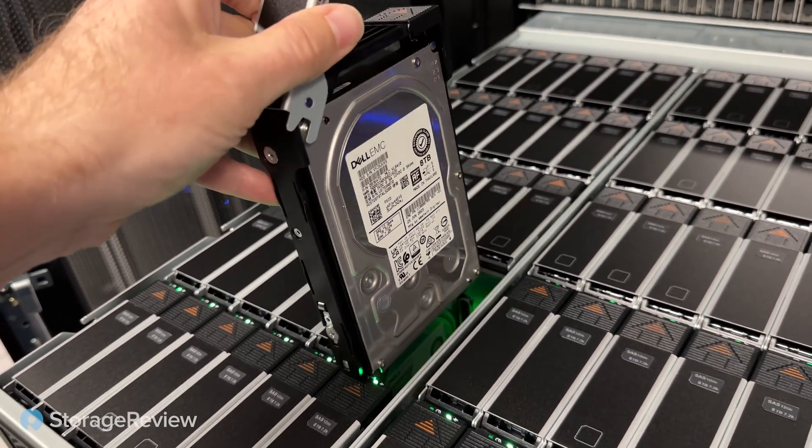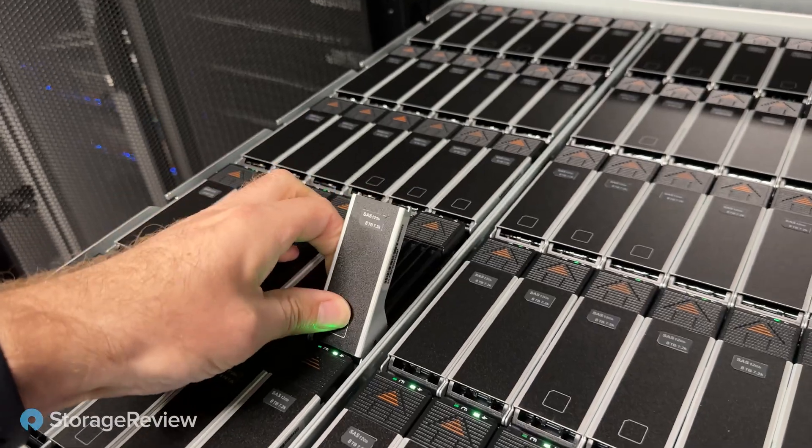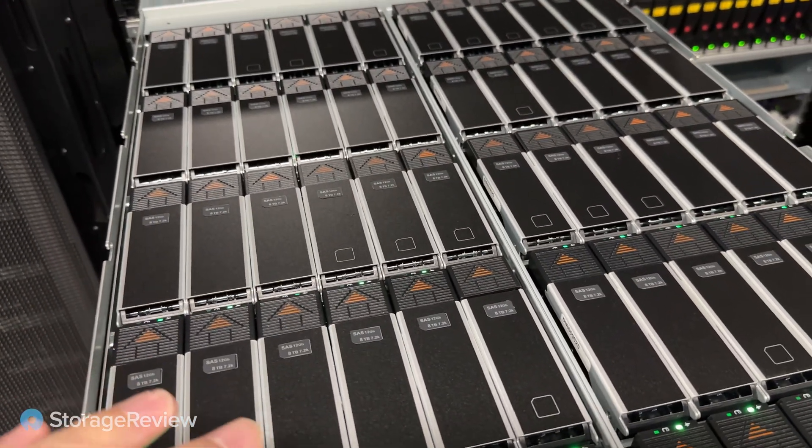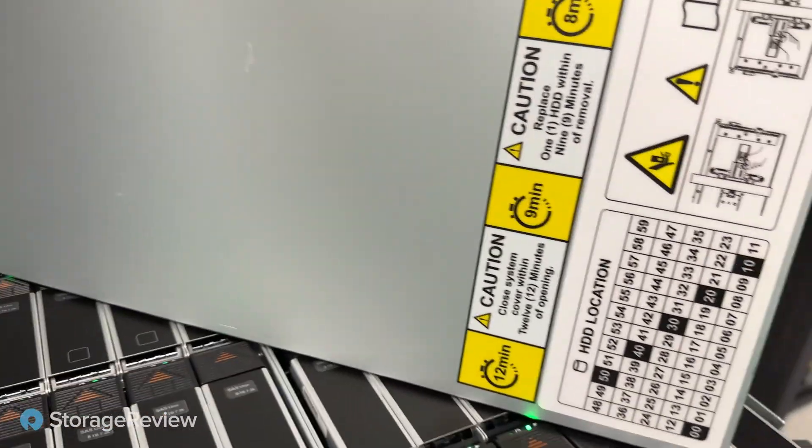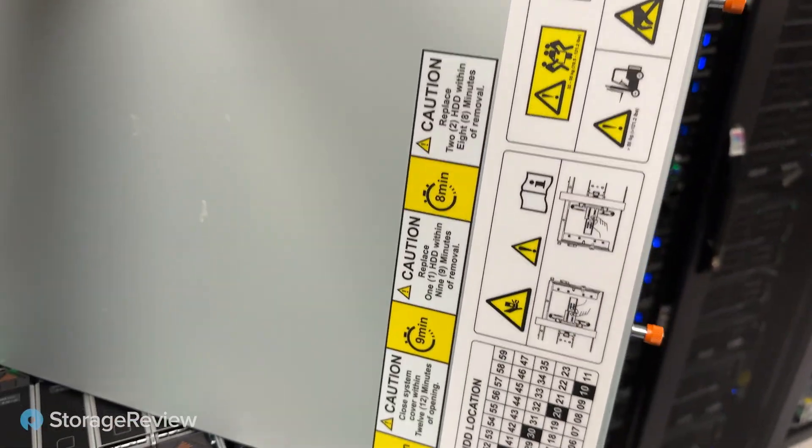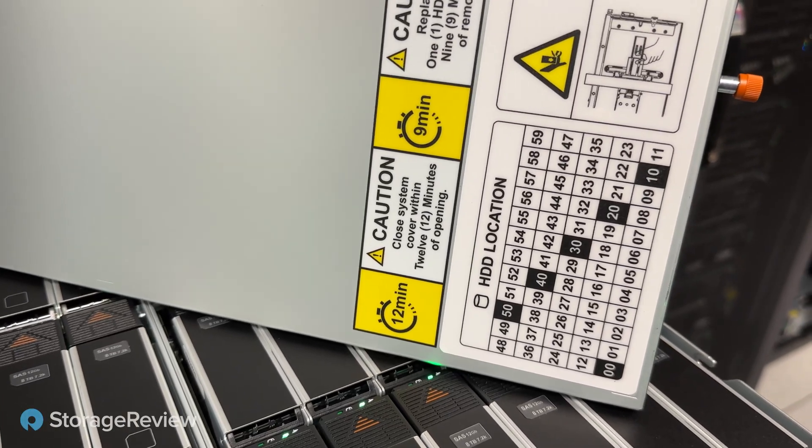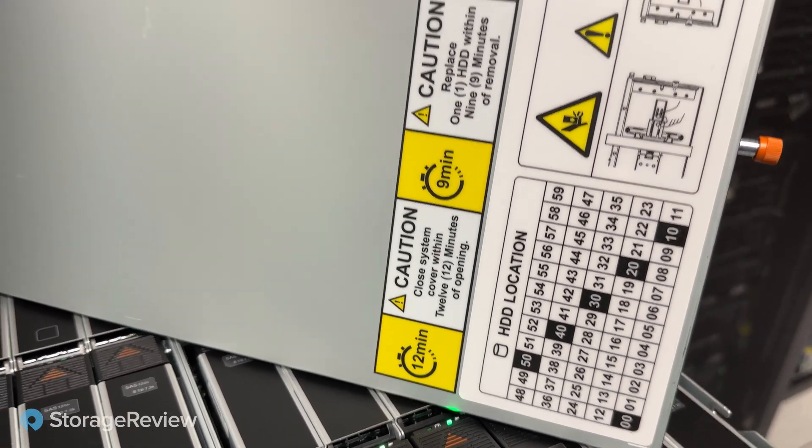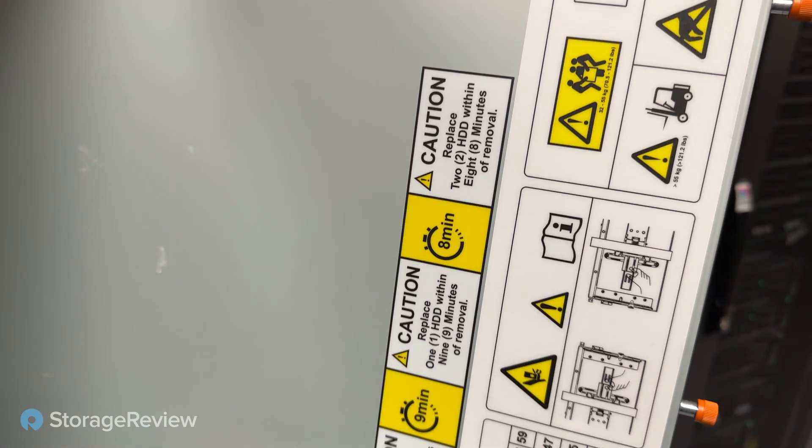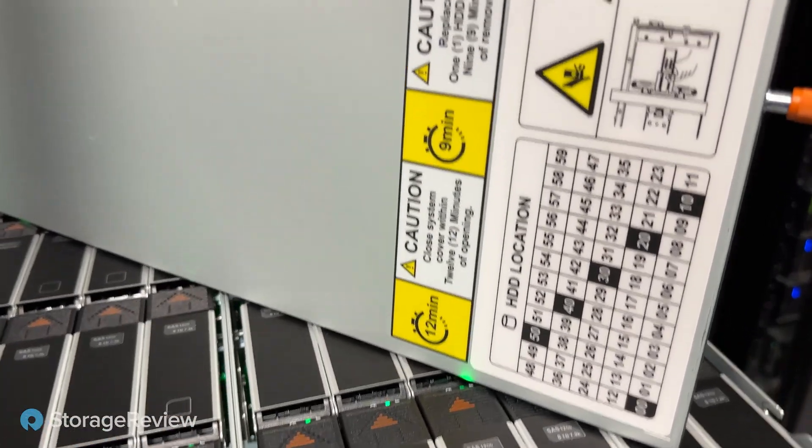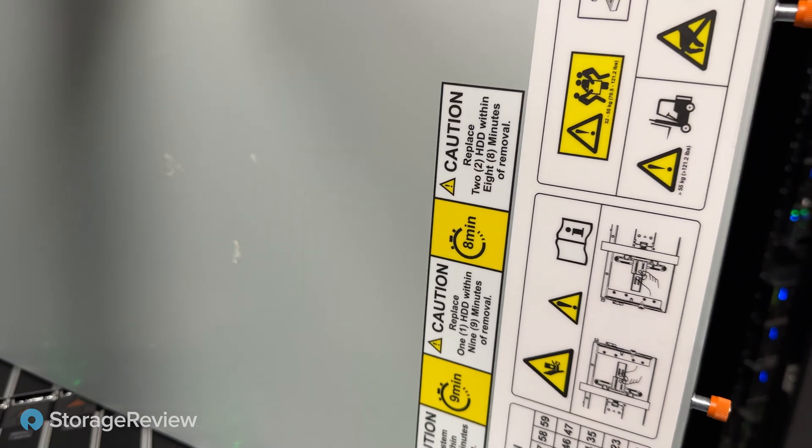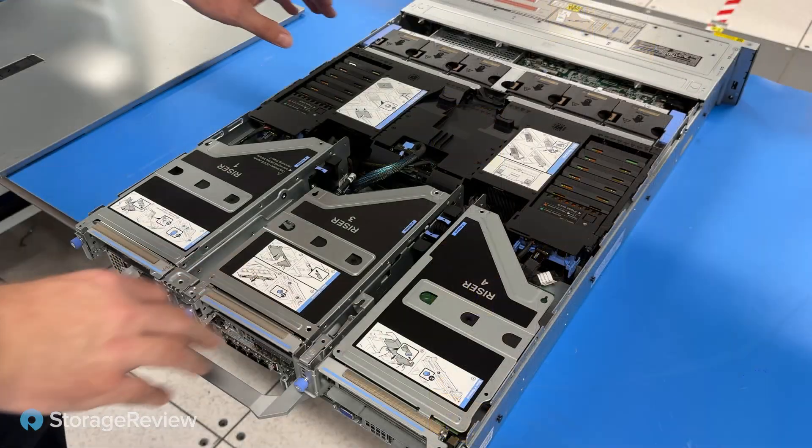Now everything is hot-swapped. These are top-loading drives. What's kind of cool is the system can handle cooling to a certain extent during servicing. Now to remind you what you're doing before you open it up, there's a warning label on the top of this cover. So if you're opening up the system, you have a maximum of 12 minutes. If you're removing one hard drive, 9 minutes of removal. If you're removing two hard drives, 8 minutes of removal. So overall, pretty cool label. You don't see this on many systems. And it gives you an idea of what you can do before you go in and start messing around with things.